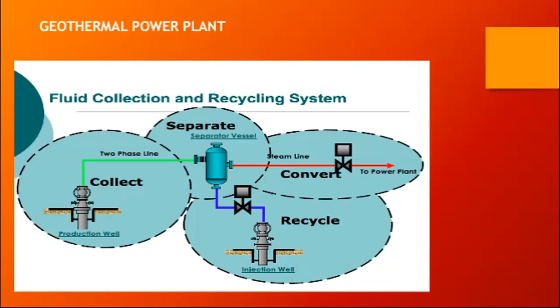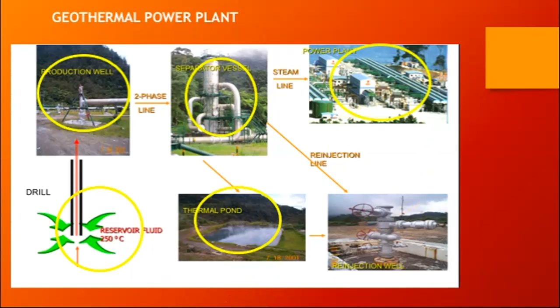Okay, some more representation of the geothermal steam field and power plant. Now let's start with the reservoir about 3 kilometers below the Earth's surface. The reservoir fluid is at 250 degrees C. Then steam moves up from the Earth through the production well. Then the two-phase fluid is channeled to a separator vessel to remove the liquid and divert the geothermal steam to the steam turbine of the power plant. And then the geothermal fluid is returned to the earth through a thermal pond and the reinjection well.